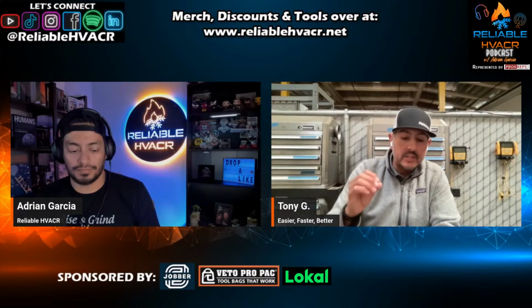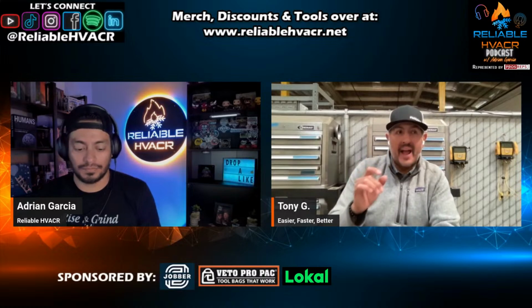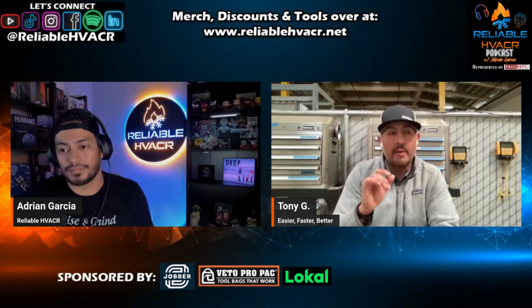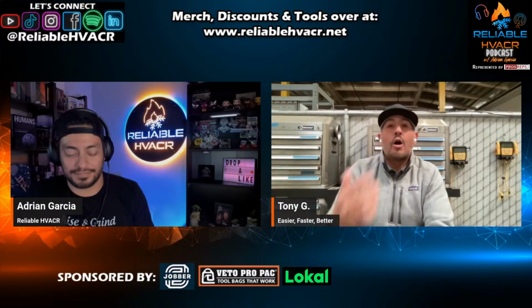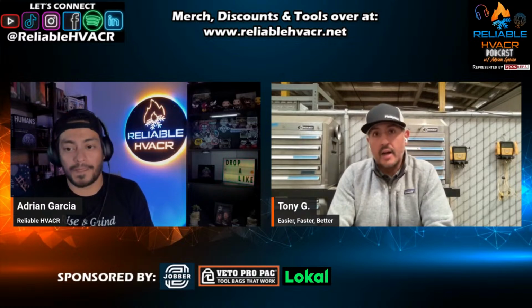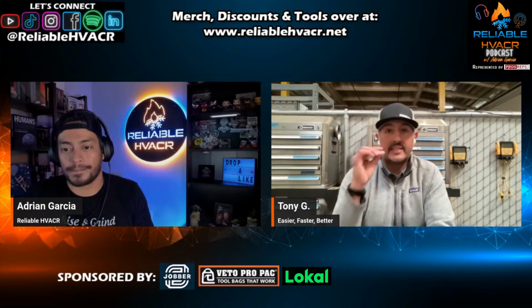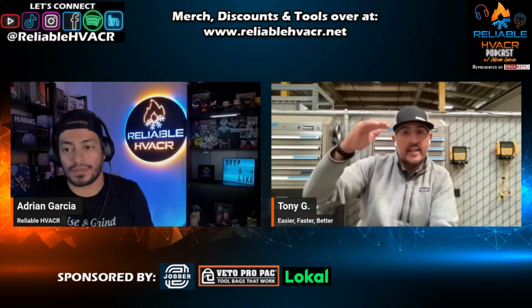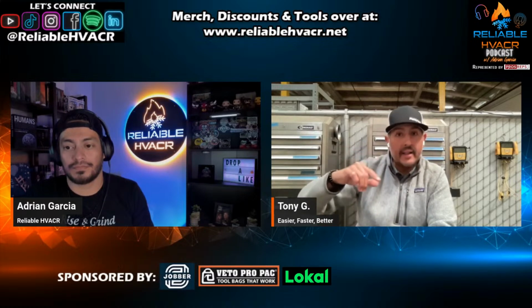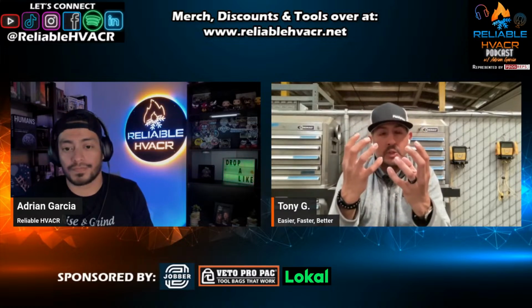And so the only thing that we need to be concerned about or just be cognizant of is that because these are classified by ASHRAE as slightly more flammable than our current, just slightly, barely, a smidge, there are certain devices that these newer systems are going to come with, like mitigation devices, that if there is a leak in the indoor coil, there's this sensor in the indoor coil that's going to measure the presence of refrigerant. And if that refrigerant reaches a certain threshold, mitigation devices will happen.